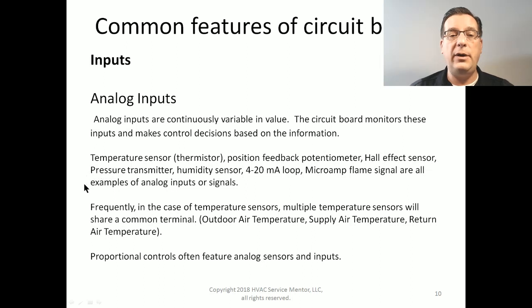A pressure transmitter. Pressure transmitters are found in modulating gas furnaces instead of a pressure switch or in addition to a pressure switch. Pressure switches will simply open or close based on a pressure set point value. So if the pressure value exceeds the set point value, the switch will close. Well, a pressure transmitter will actually transmit information about exactly what the pressure is. It will sense the pressure, and it will send out a proportional signal describing what the pressure value actually is. Other examples are humidity sensors, 4 to 20 milliamp loops, and microamp flame signal. That is an example of an analog input.